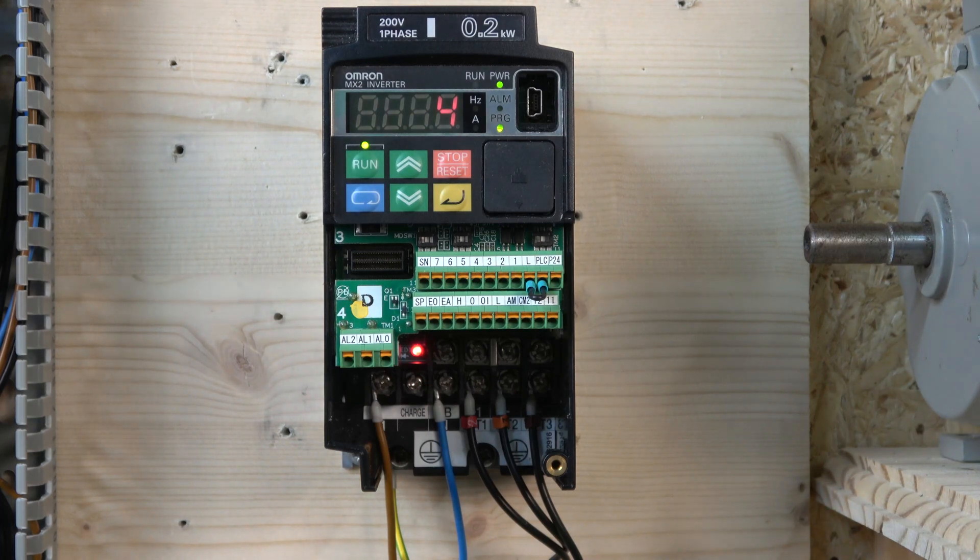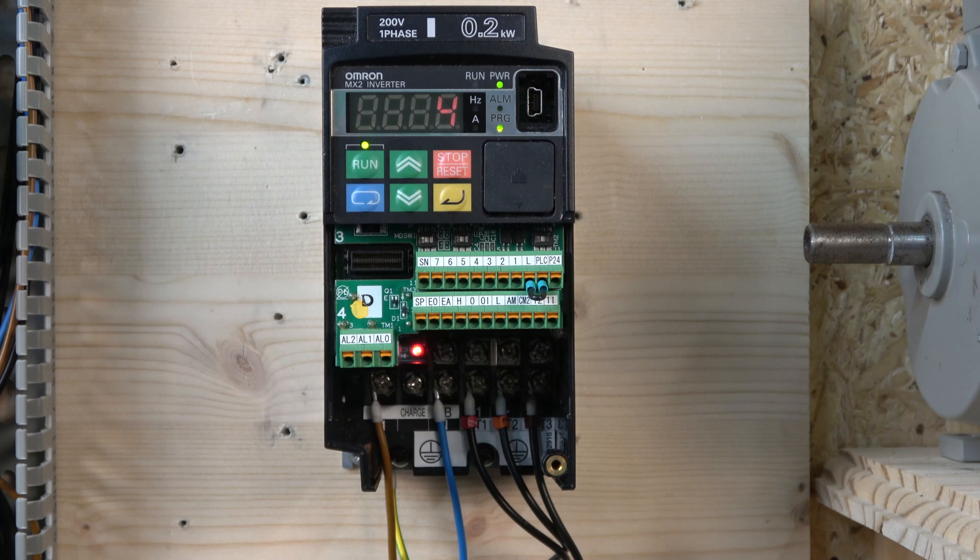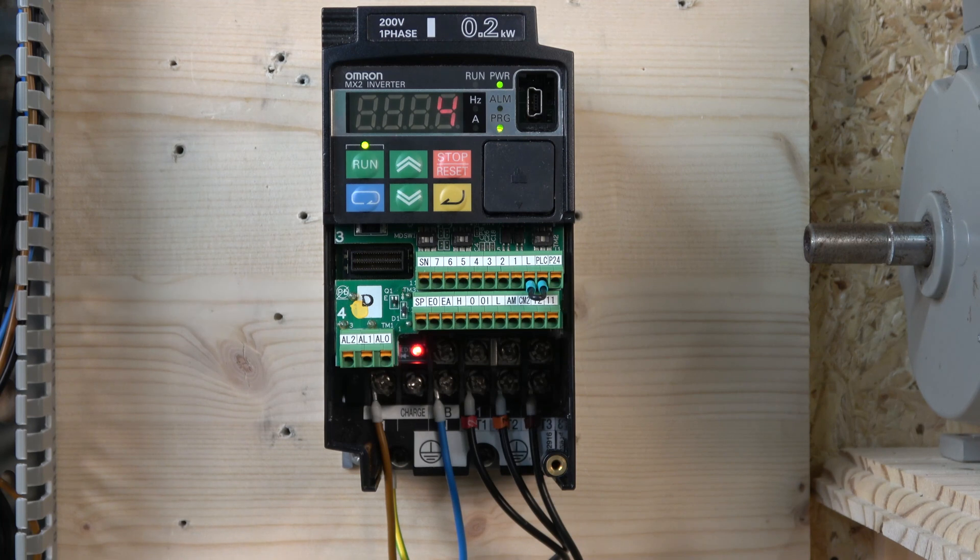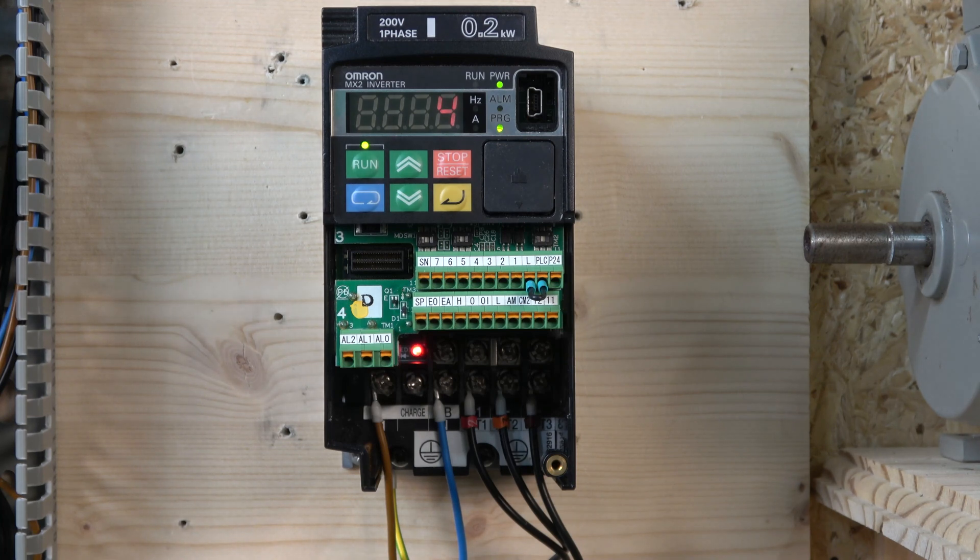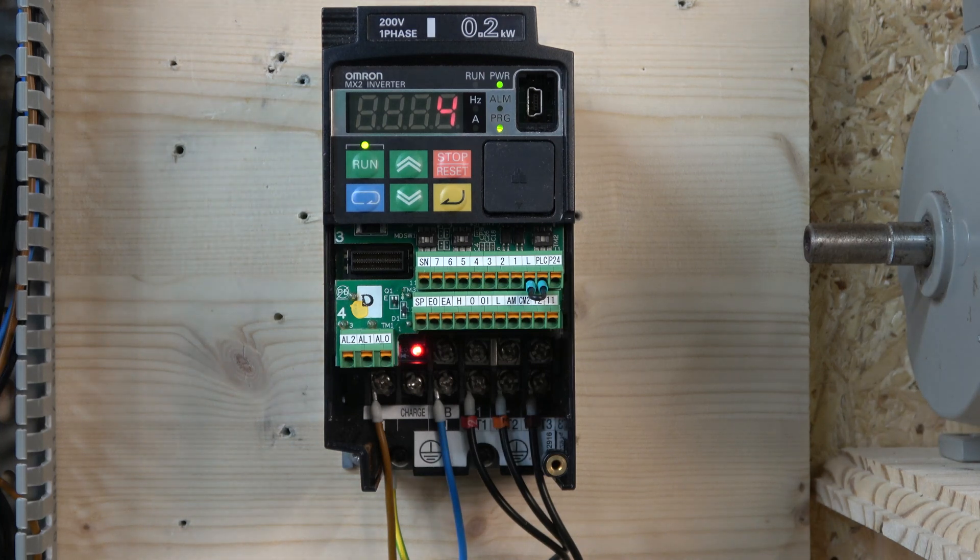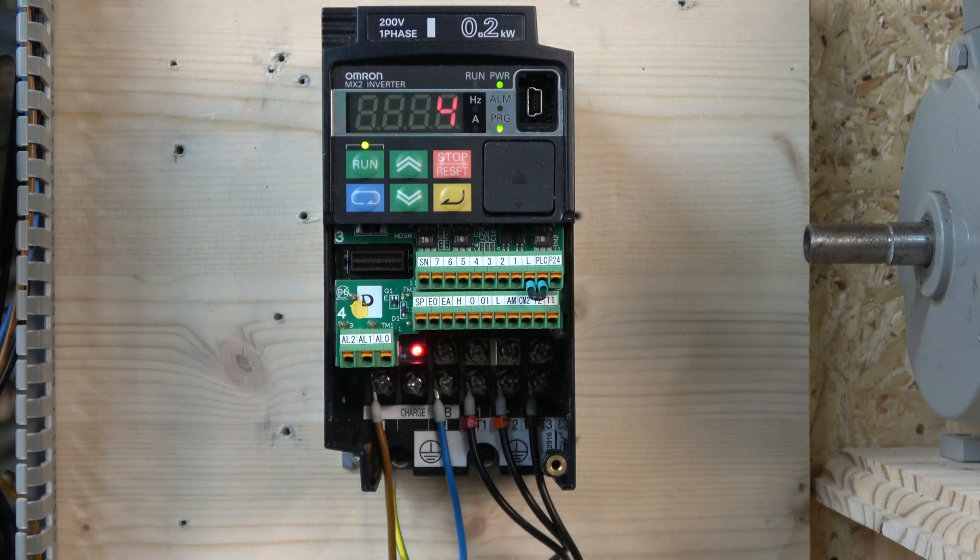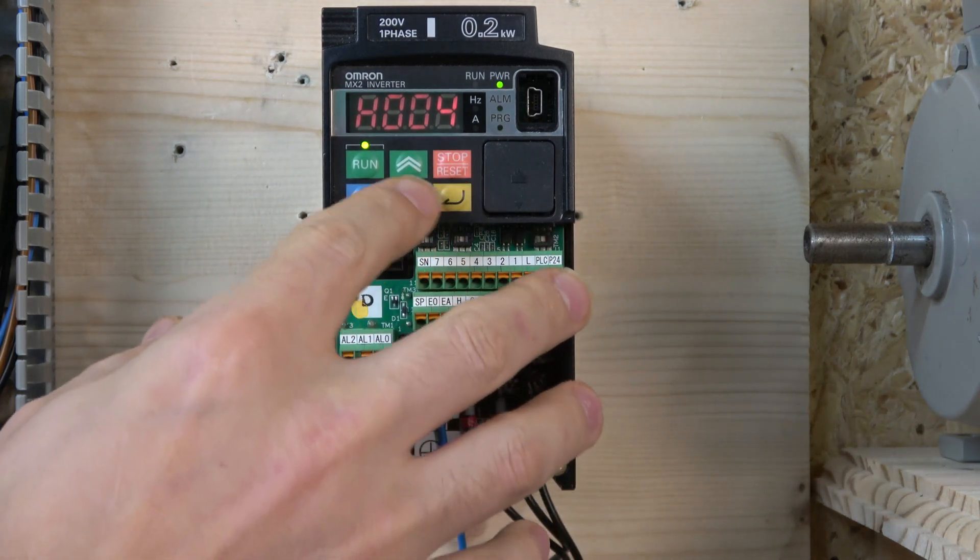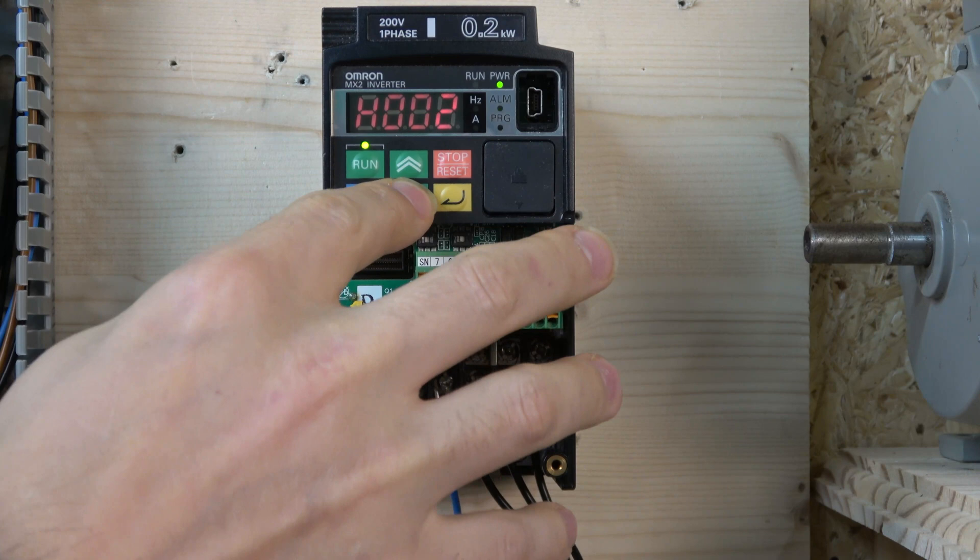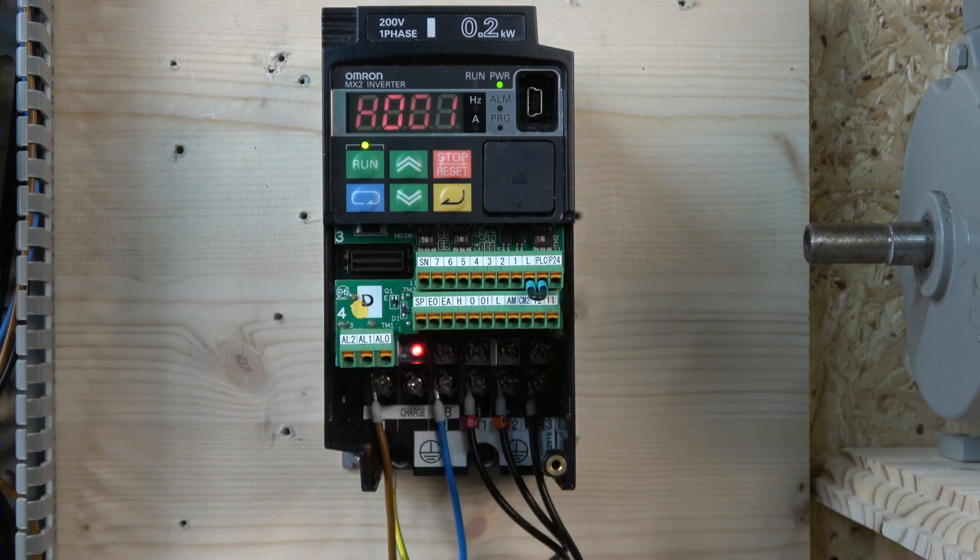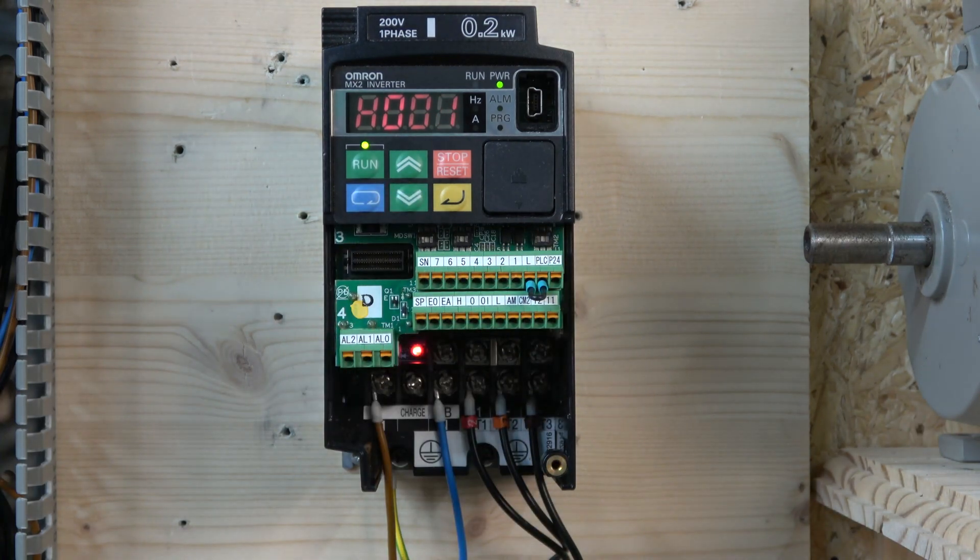The following is going to be H4. H4 stands for the poles - how many poles your motor has. Just to give you a quick explanation, it's quite often you can see that by the RPM. If your motor is around 1400-1500 RPM, you're on four poles. If you're two pole, it would be like 3000. If you're six pole... but do check out online how to identify how many poles your motor has. It's related to the RPM as well.